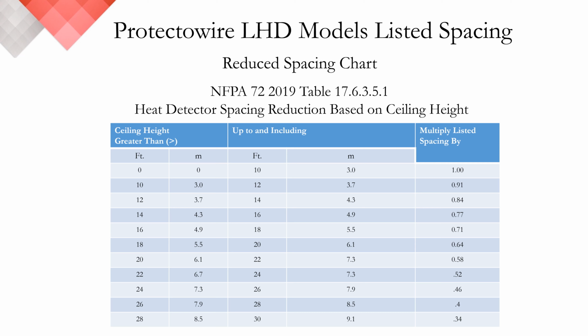As referenced here, all listed spacing is based on a 10-foot smooth ceiling, but as we all know, that's just the tip of the iceberg. More often, we're dealing with ceiling heights ranging much higher than 10 feet and typically over 100 feet. This table shows the required reduction factor based on the physical height of the ceiling the device is going to be installed. As the ceiling height increases, the effective spacing of the detector decreases.